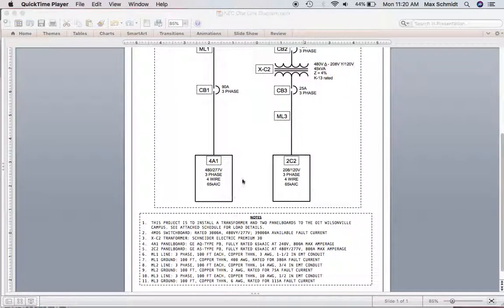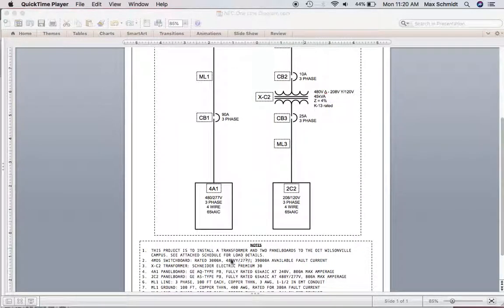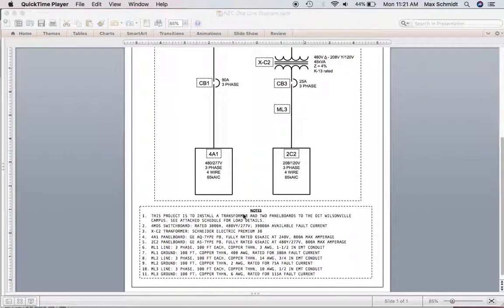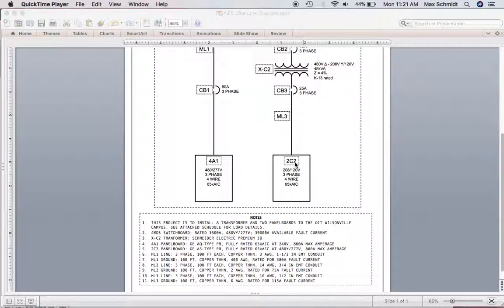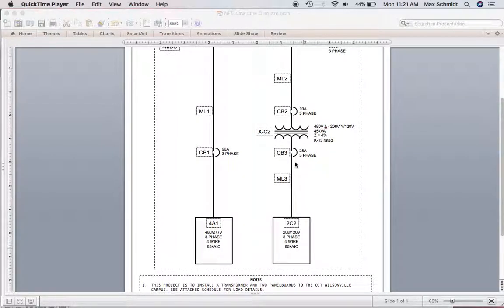And then for the panel boards, I sized those by looking at my available fault current from the utility bus, and that was 39 kiloamps. So each of these is rated to handle well over that at their rated voltage, which is great. So for my 4A1 panel board, I selected an AQ type GE panel board, and then for my 2C2, it's going to be an AS type panel board.